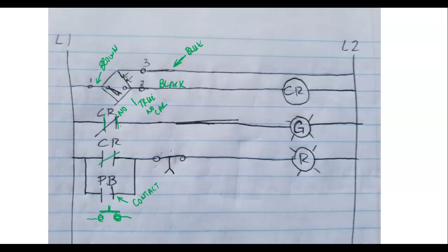Now what's wrong with this one? First of all, I don't see a timer anywhere. I see a CR, I see a G, I see an R. You have a timer contact, normally closed, right? But we don't have anything - this needs to come all the way over here. So we have no timer coil on the right hand side. Y'all see that?